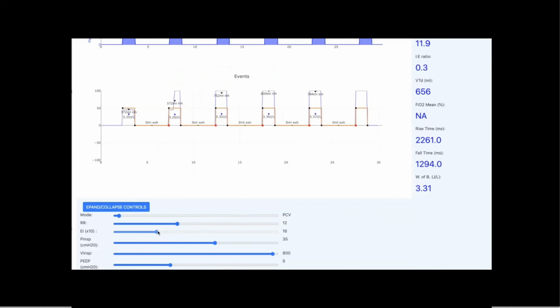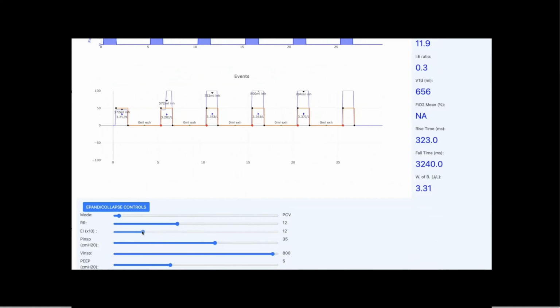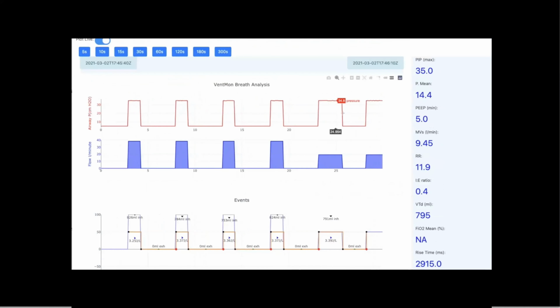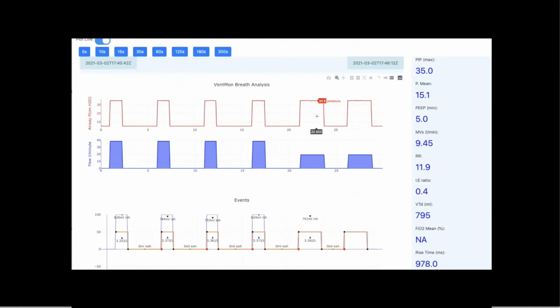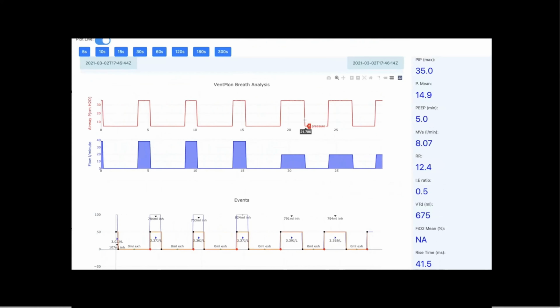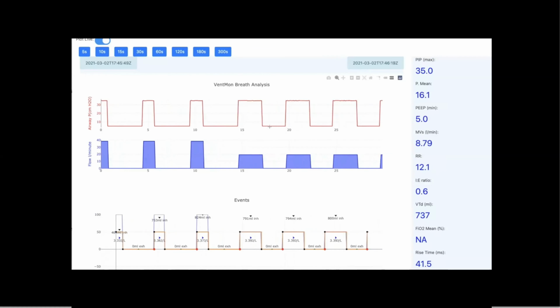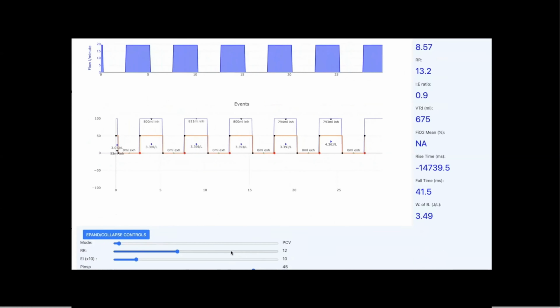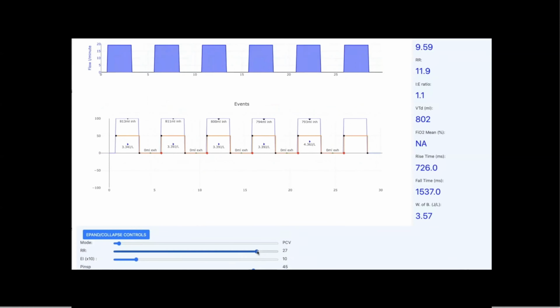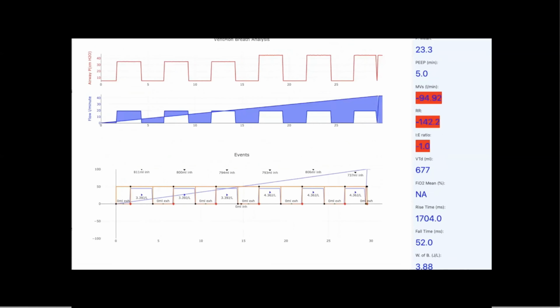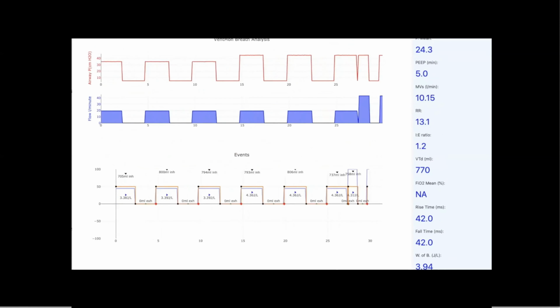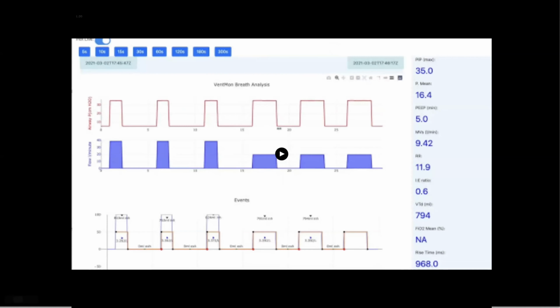Now we can change the exhalation to inhalation ratio to something closer to one. You can see the pressure wave now has the same inhalation period, where pressure is being applied, as the exhalation period, which drops to the so-called PEEP. I can also increase the respiratory rate, which will make it go faster, but will necessarily make each breath shorter. That was a display of the system working as it currently stands.